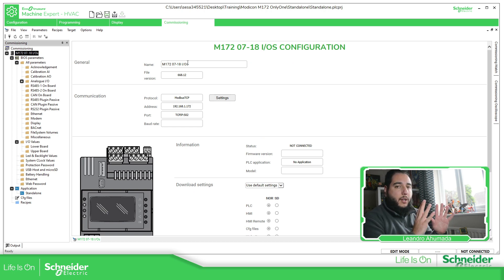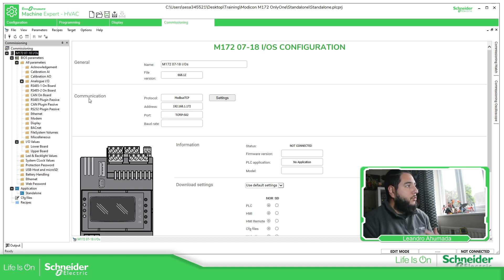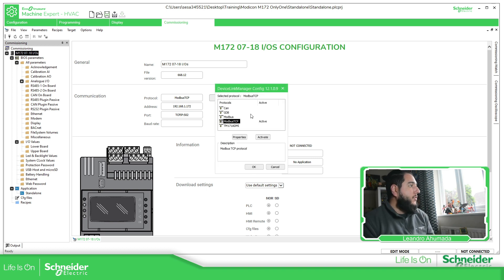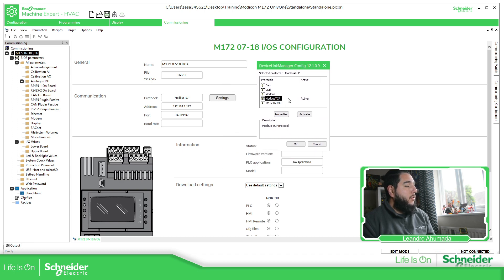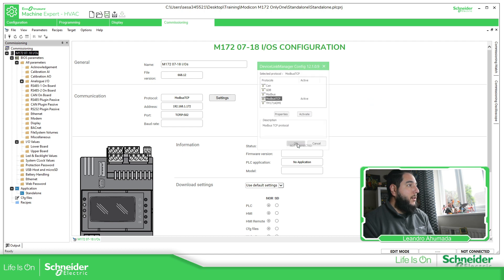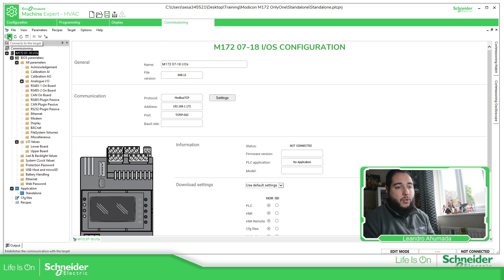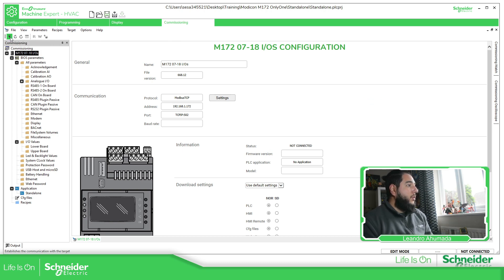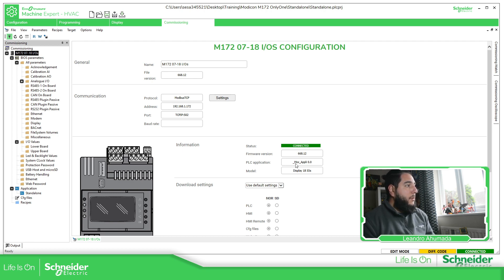Going back to the commissioning tab, clicking on it shows information about the device configured in the software — not the one on the controller. To connect to the controller I need to specify how I'm going to communicate. By default it's configured as Modbus TCP, so I'll use an Ethernet connection. I go to Properties to define the IP address of the controller. Now I use the connect button to connect to the controller.